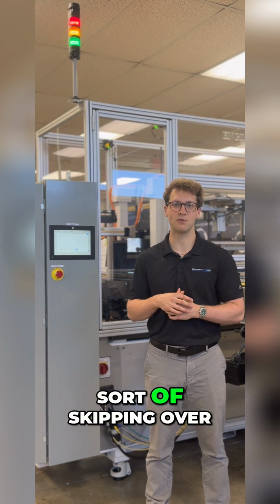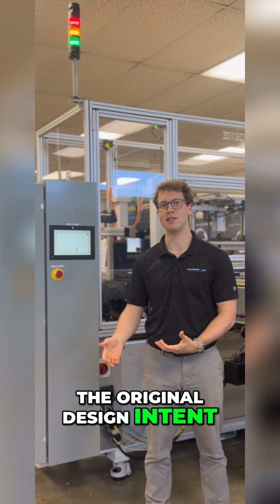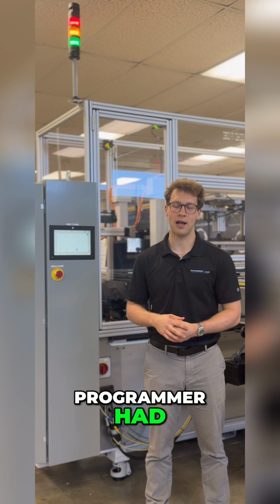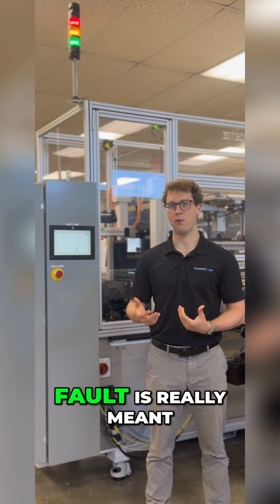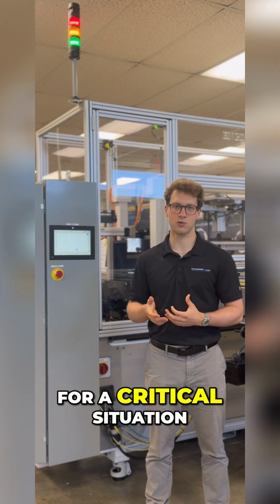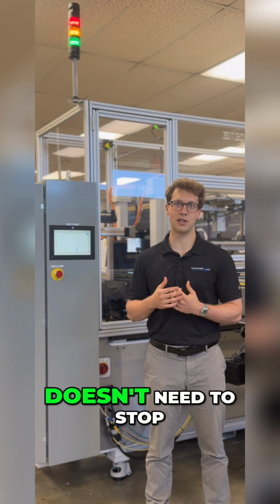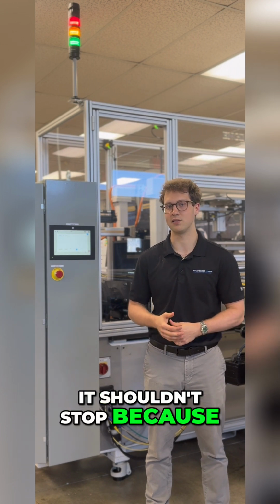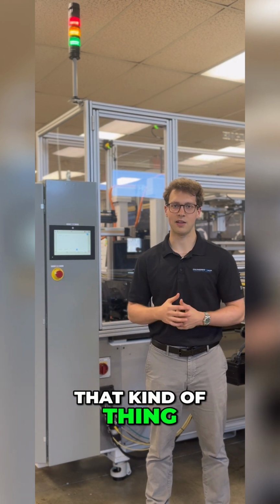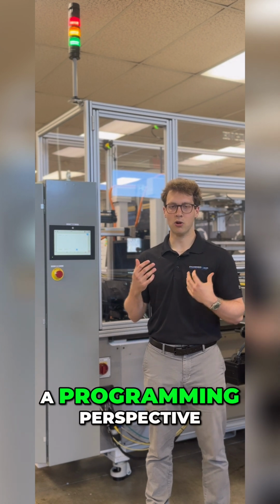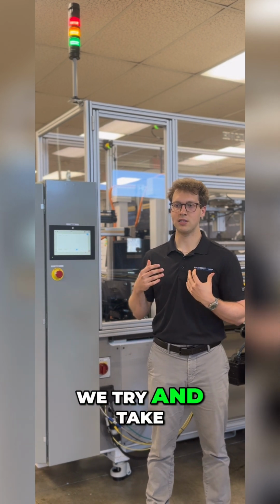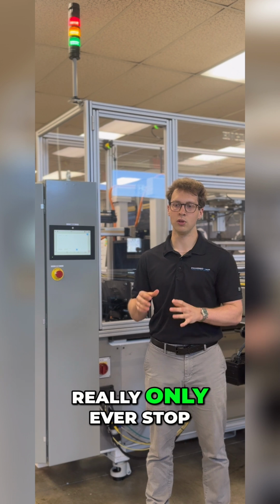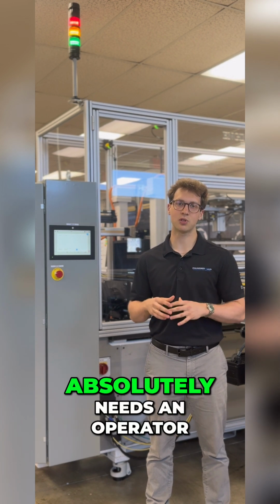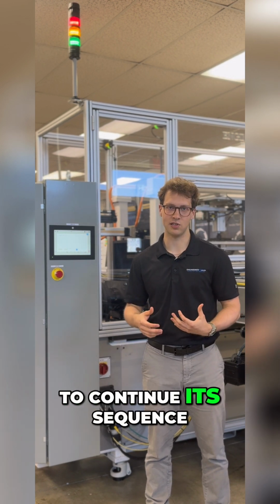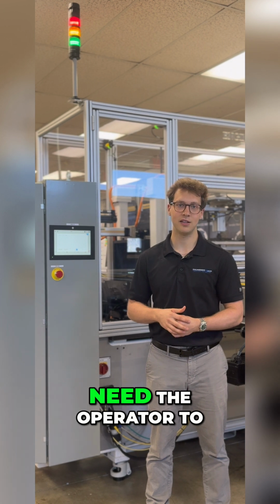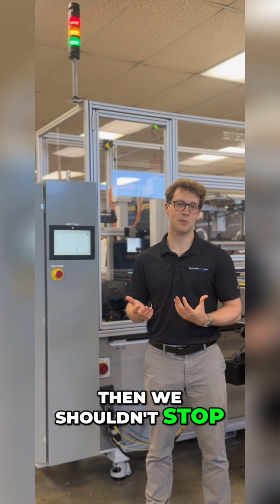One, they're sort of skipping over the original design intent that the programmer had. But then two, the fault is really meant for a critical situation. And if the machine doesn't need to stop, it shouldn't stop, because then it causes downtime, that kind of thing. So from a programming perspective, we try and take the best approach and really only ever stop the machine when it absolutely needs an operator to continue its sequence. And if it doesn't need the operator to do something, then we shouldn't stop the machine.